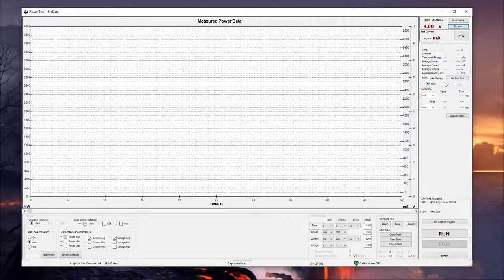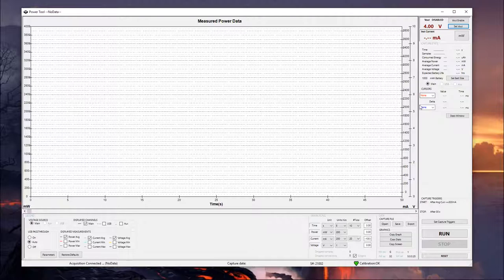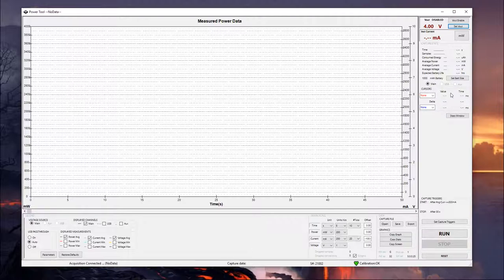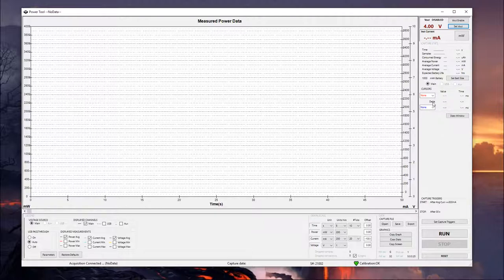You also have three different channels here. So if you're measuring on something other than the main channel, you would select the appropriate channel here. And it would change these statistics depending on which channel you have. The cursors I'm also going to show you a little bit later. But it's a useful way to identify how large peaks are, time differences, or differences between a high and low peak, kind of things like that. And I'll show you that a little bit later.